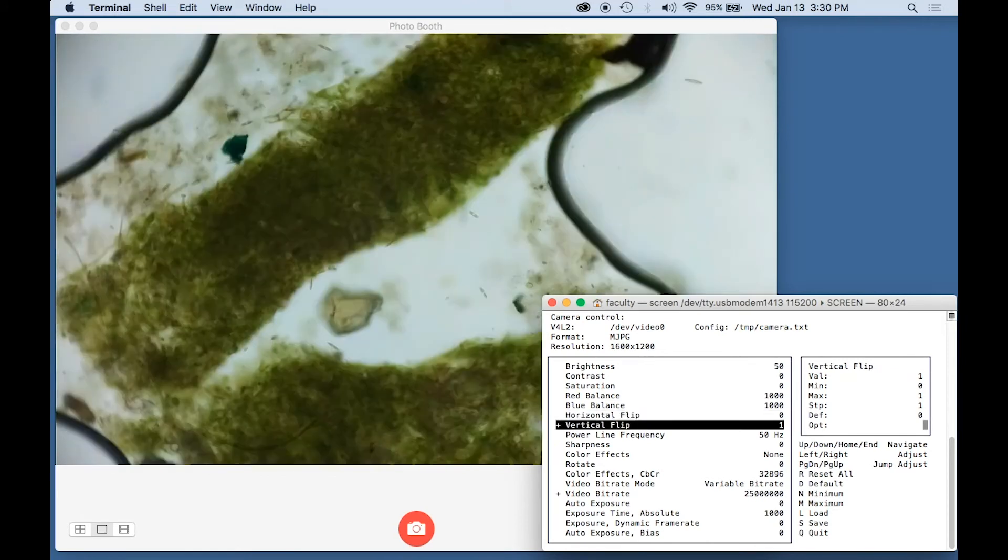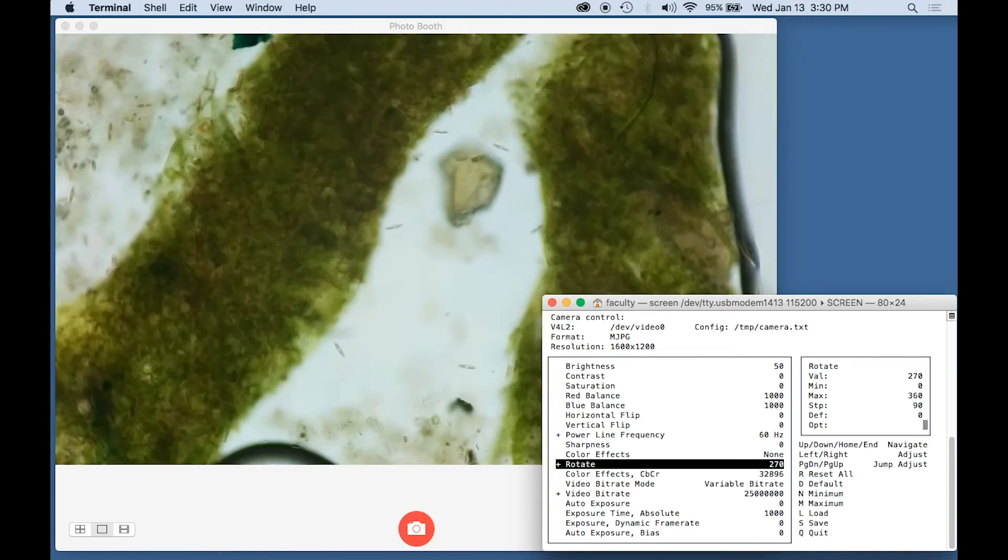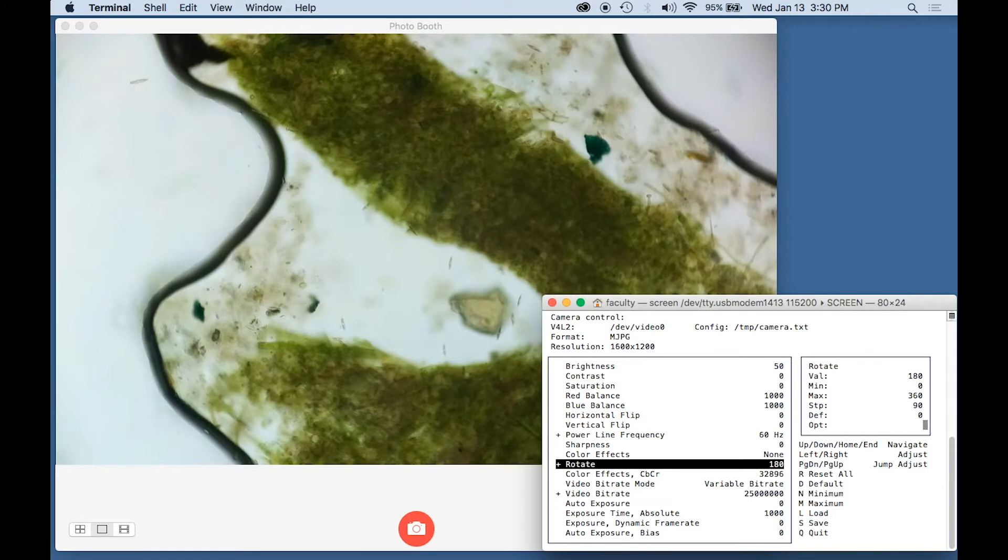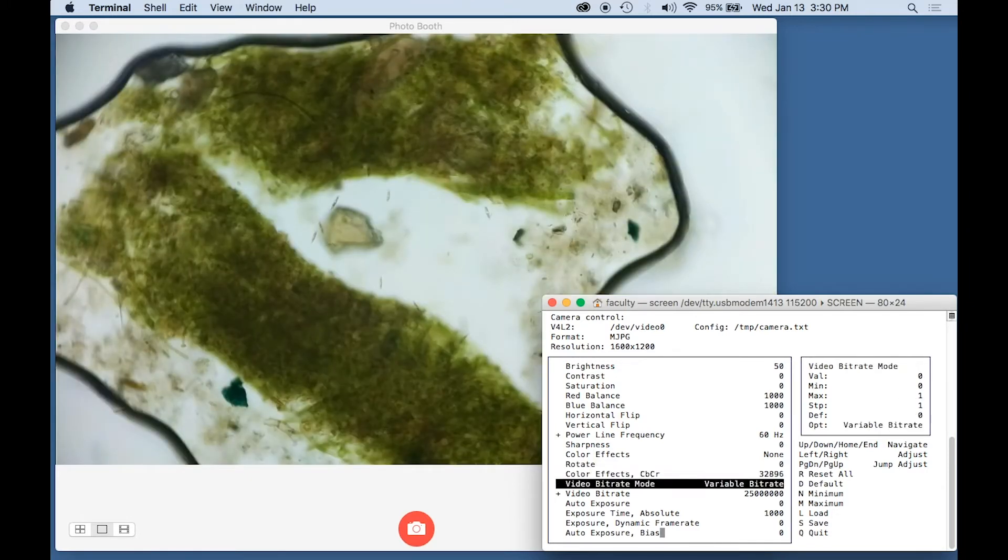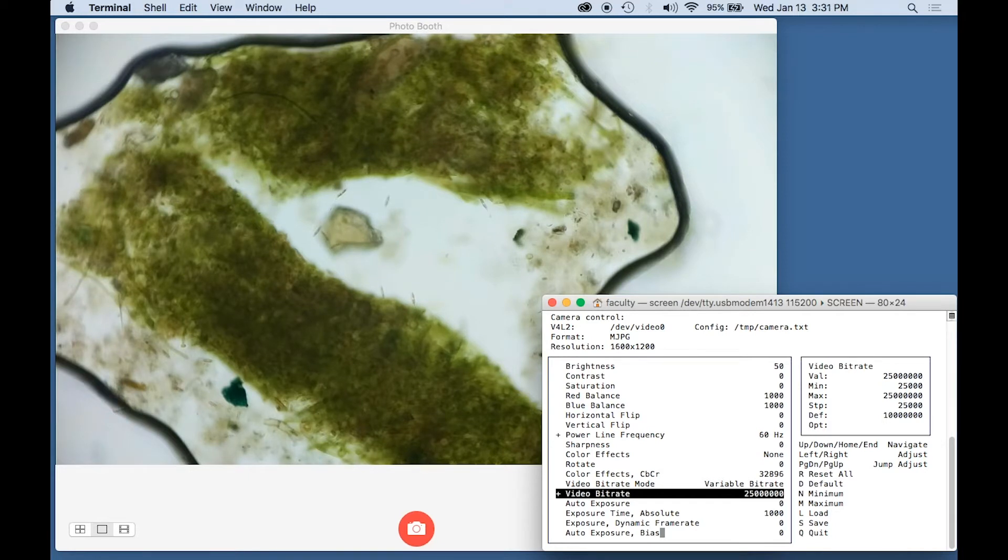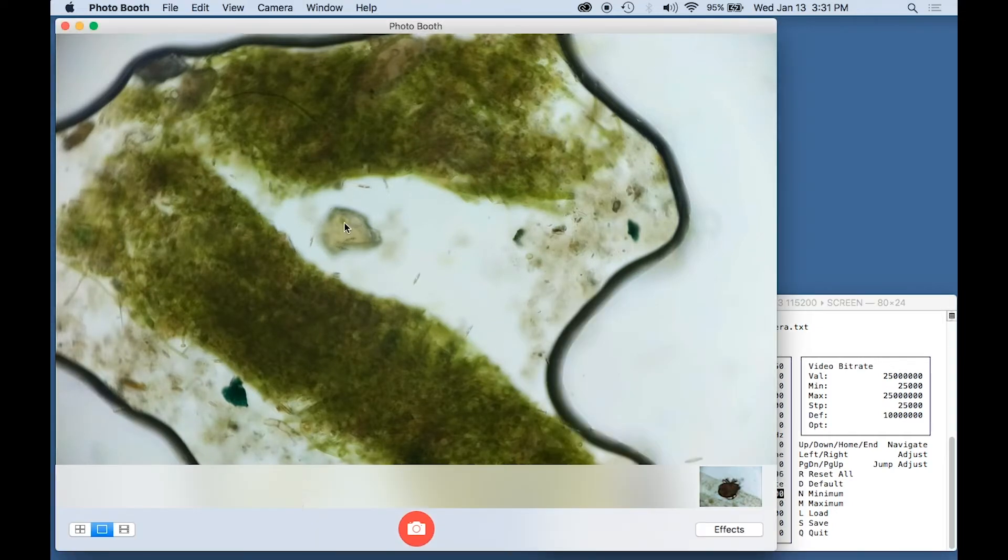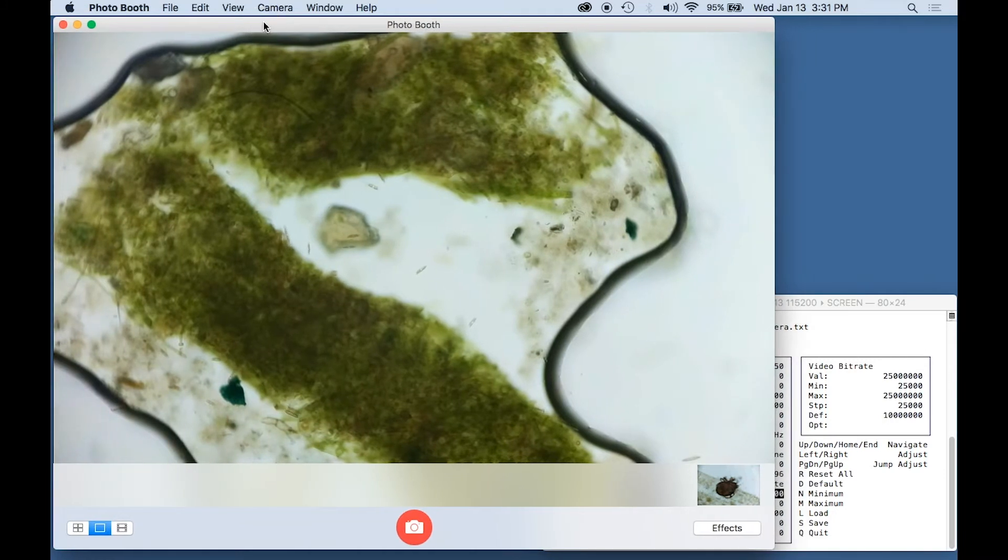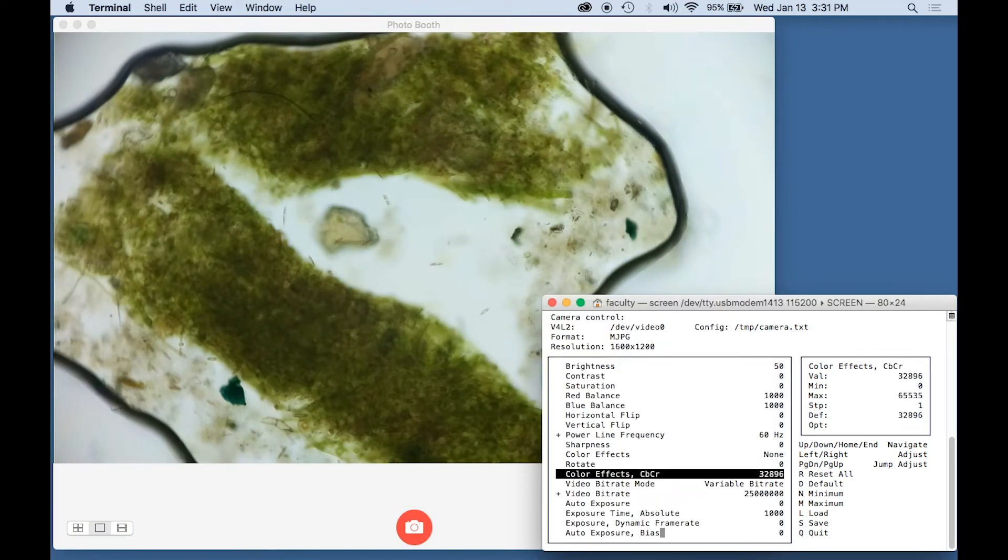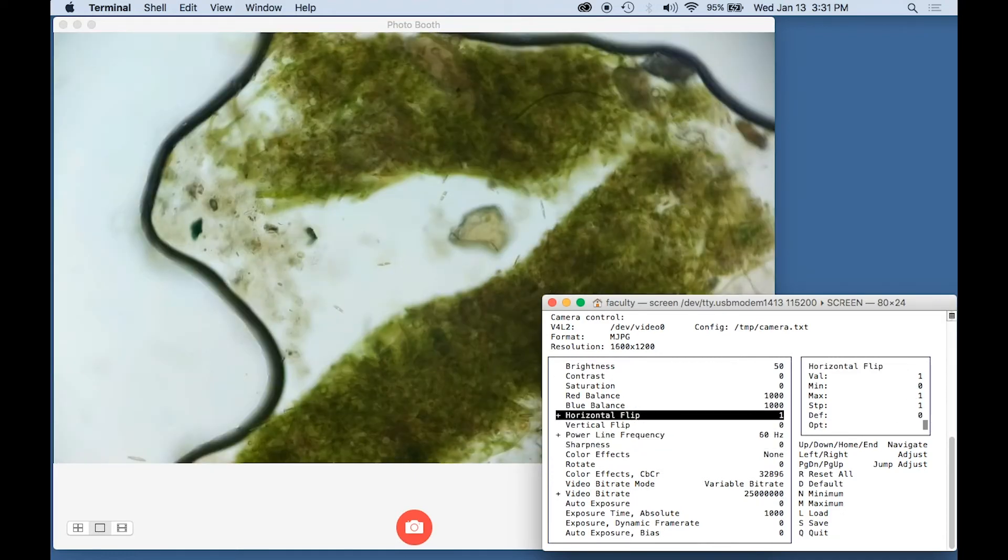That is the flip. That is another flip in the other direction. One thing that you should know is that Photobooth shows you a mirror image of the image. But when you actually save the video or the still picture, it will be exactly flipped from what you see. It will be what you see in the microscope. Don't be fooled and change the horizontal flip to make it appear like the eyepiece, because when you save the image, it will be flipped. But if you are in a presentation, let's say you're in Zoom and you're sharing the image from Photobooth, then you do want to use the image control to flip the image so that what is being shared is exactly what you see on your screen.